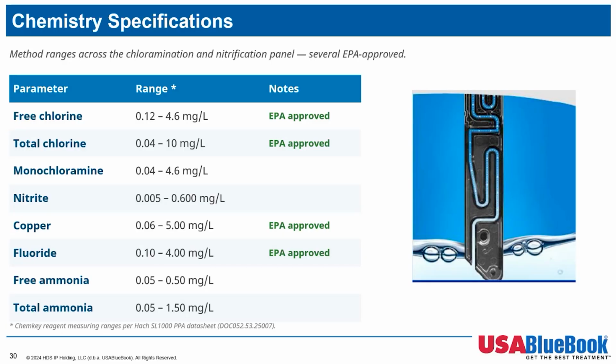So talking about the trust of the measurement, noisy readings or odd kinetics, this will stop and give you a message. If one of these chem keys, shown here on the screen in detail, is not sealed or seated properly, the instrument will give you a message regarding aspiration or leak error, not a false number. It also flags a used chem key, an expired lot, and a sample that is too warm. An error you can fix beats an incorrect result you would have otherwise reported.